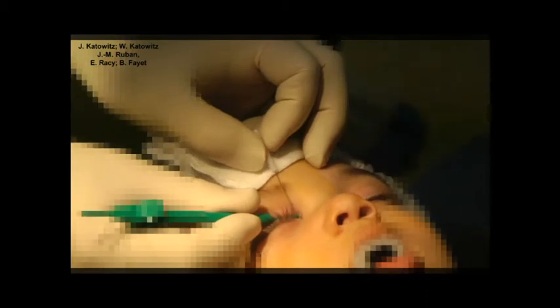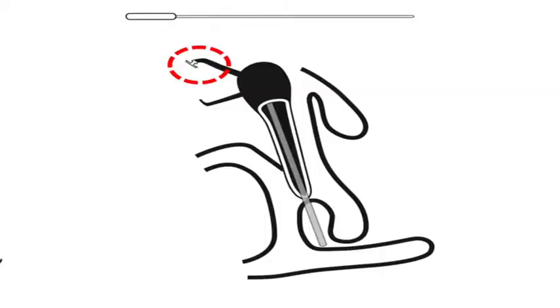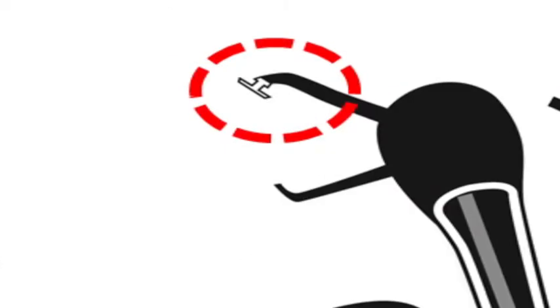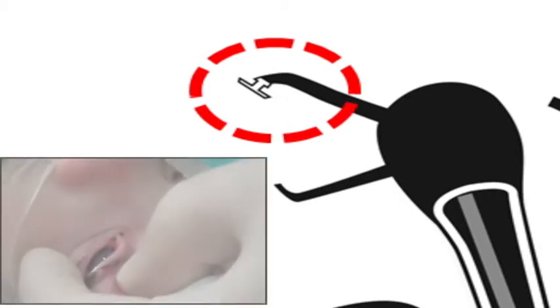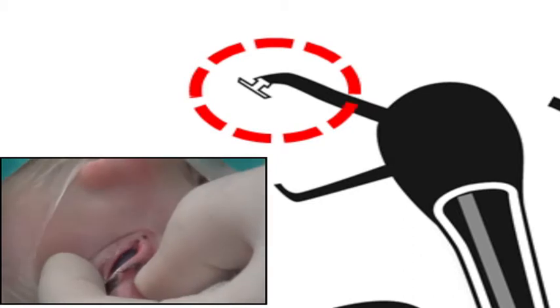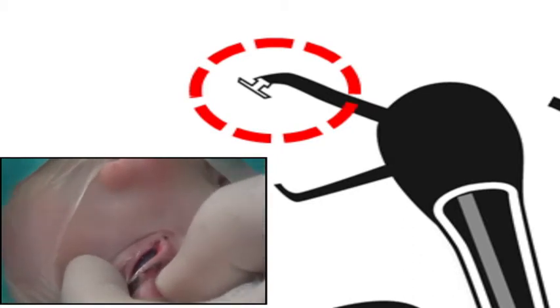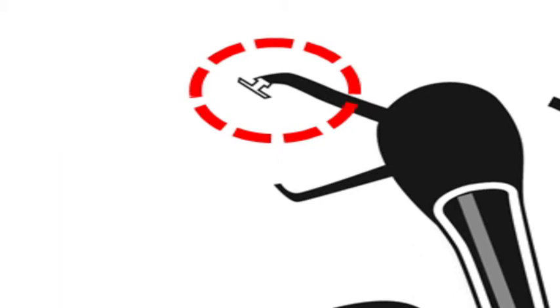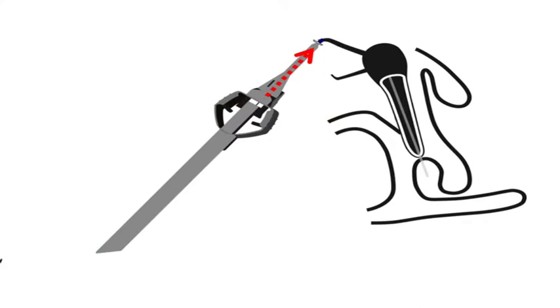The rotating movements should be continued until the insertion guide has been completely removed. It is then essential to check two things. First, that the fixation head remains in close contact with the punctum without having a tendency to pop out, and second, that it does not pass through the punctum and become buried in the canaliculus. This is especially important since the silicone stent is then no longer visible and can be difficult to retrieve.